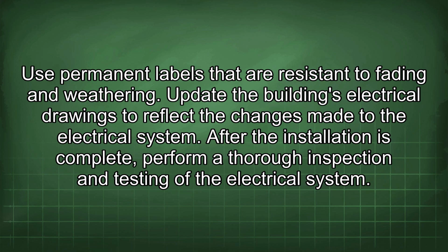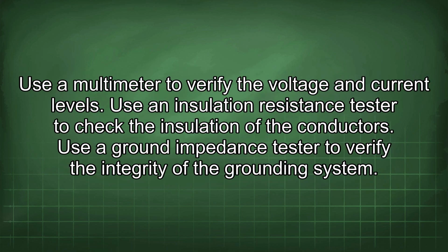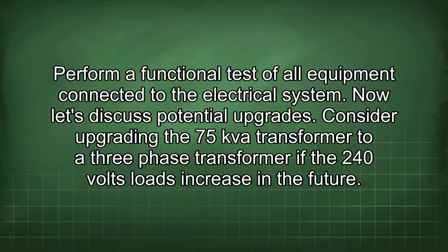After the installation is complete, perform a thorough inspection and testing of the electrical system. Use a multimeter to verify the voltage and current levels. Use an insulation resistance tester to check the insulation of the conductors. Use a ground impedance tester to verify the integrity of the grounding system. Perform a functional test of all equipment connected to the electrical system.